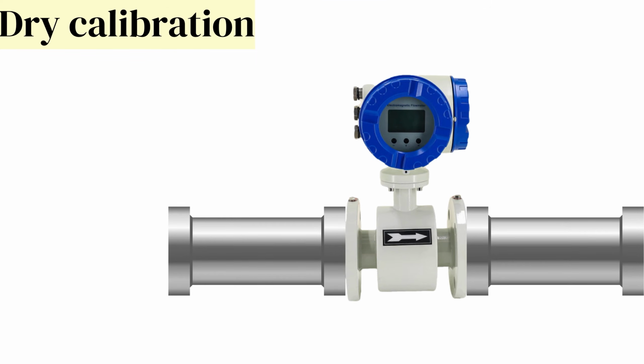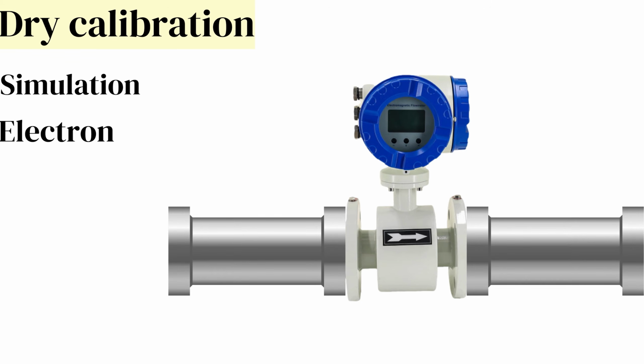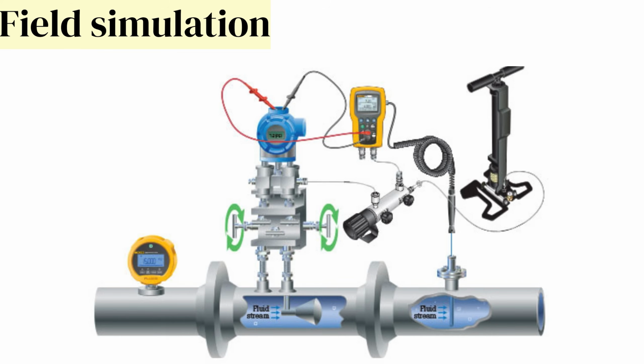Dry calibration. Dry calibration, also known as simulation or electronic calibration, does not require the flow of liquid. Instead, it uses electronic signals to simulate a flow condition, and the flow meter's response is checked against expected values. Types of dry calibration are: 1. Field simulation. For in situ calibration, technicians use a calibration device that generates a current or voltage signal simulating specific flow conditions. The flow meter's response is then compared to these simulated values.